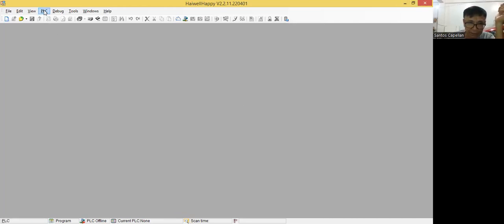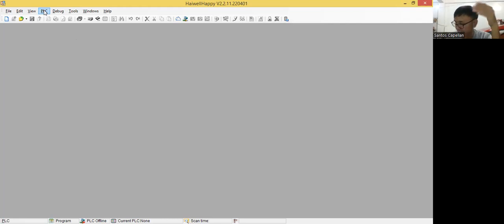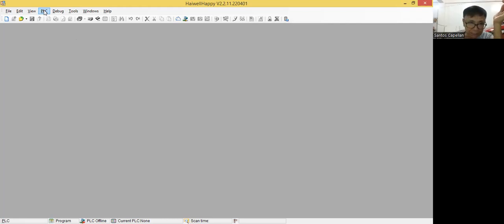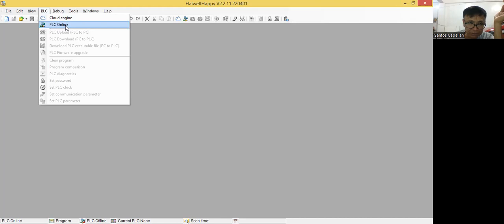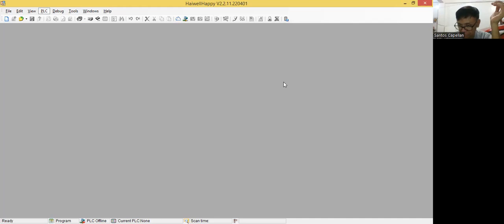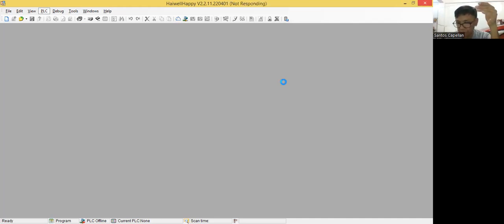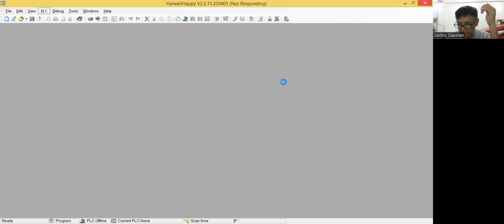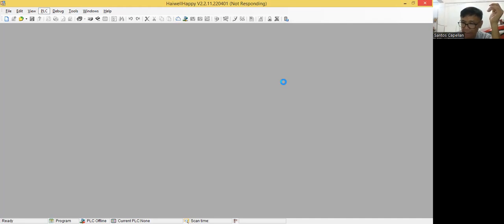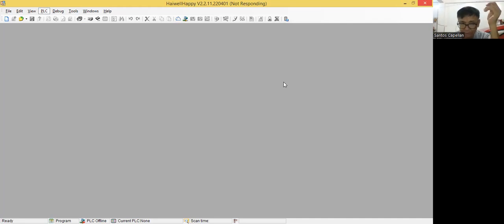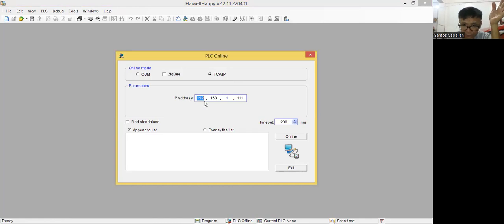Now actually, the network for this PLC is TCP IP. So let me make it online, just to show you. Just give me a minute. So we will try to make the PLC online so that we can see the program uploaded to it. Now, for the PLC online, the network is TCP over IP. Then the default IP address is 192.168.1.111.